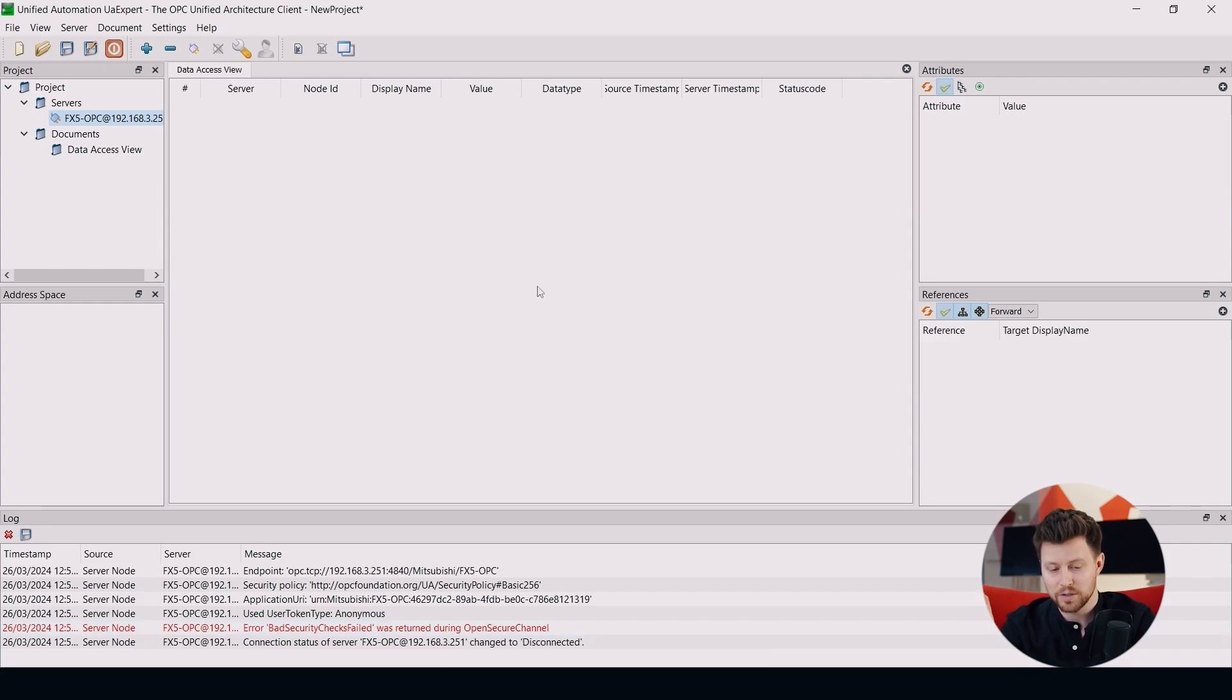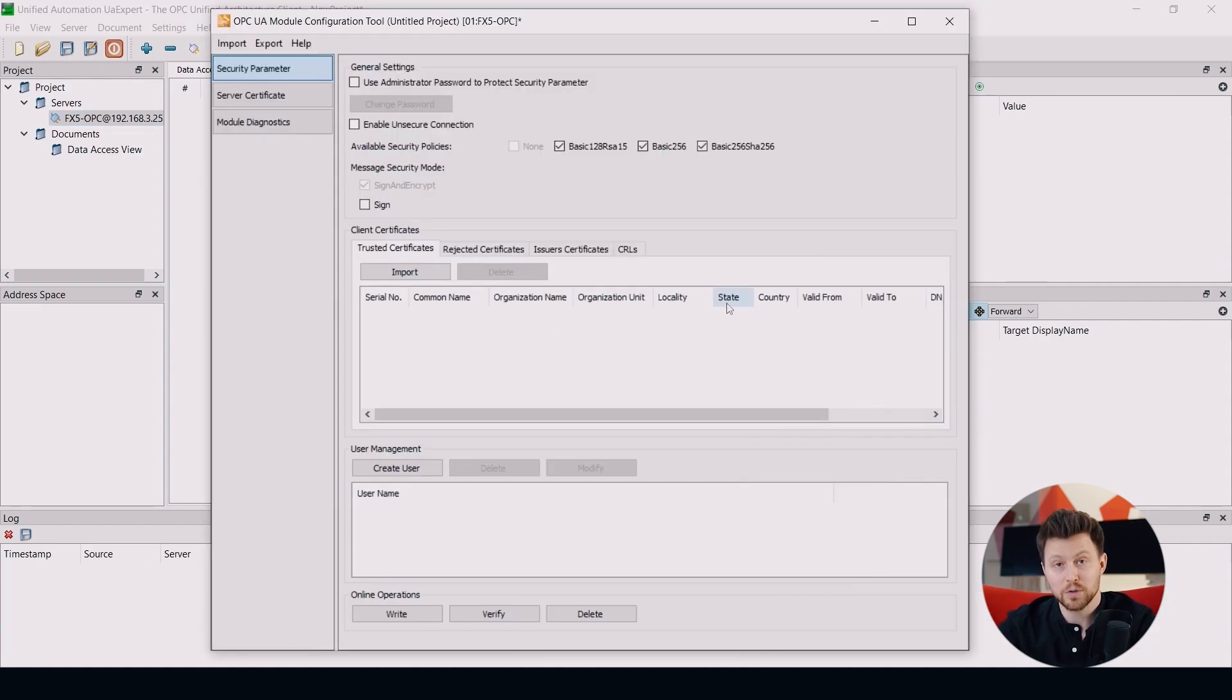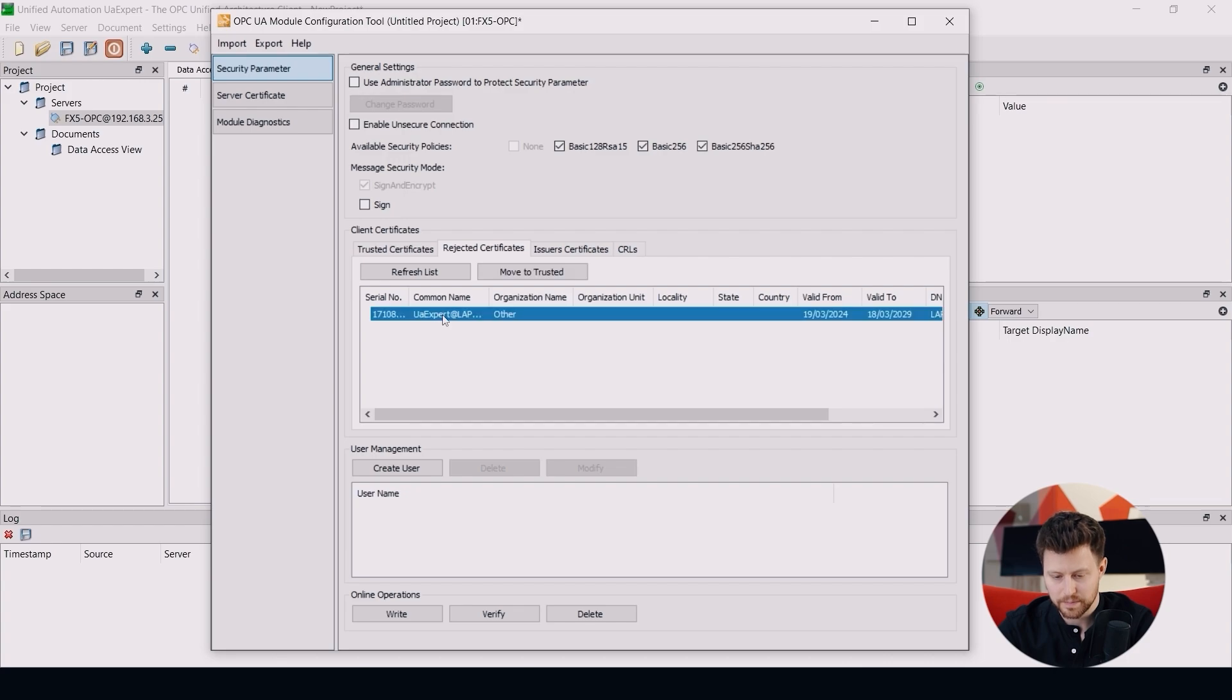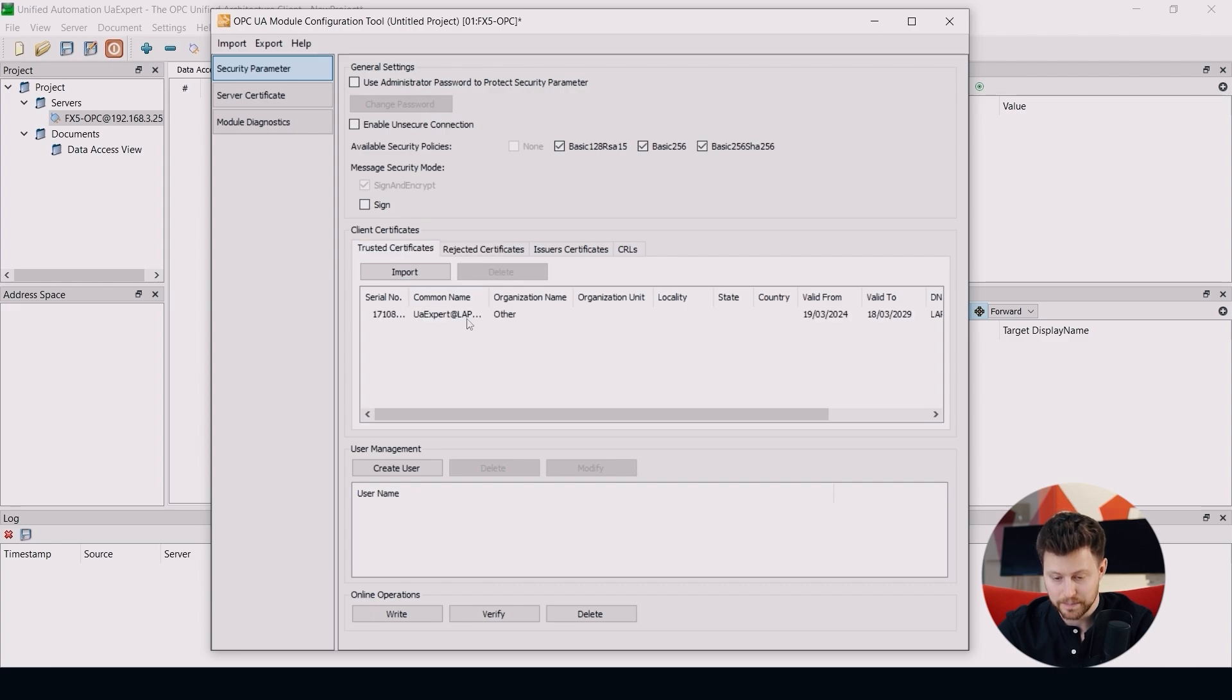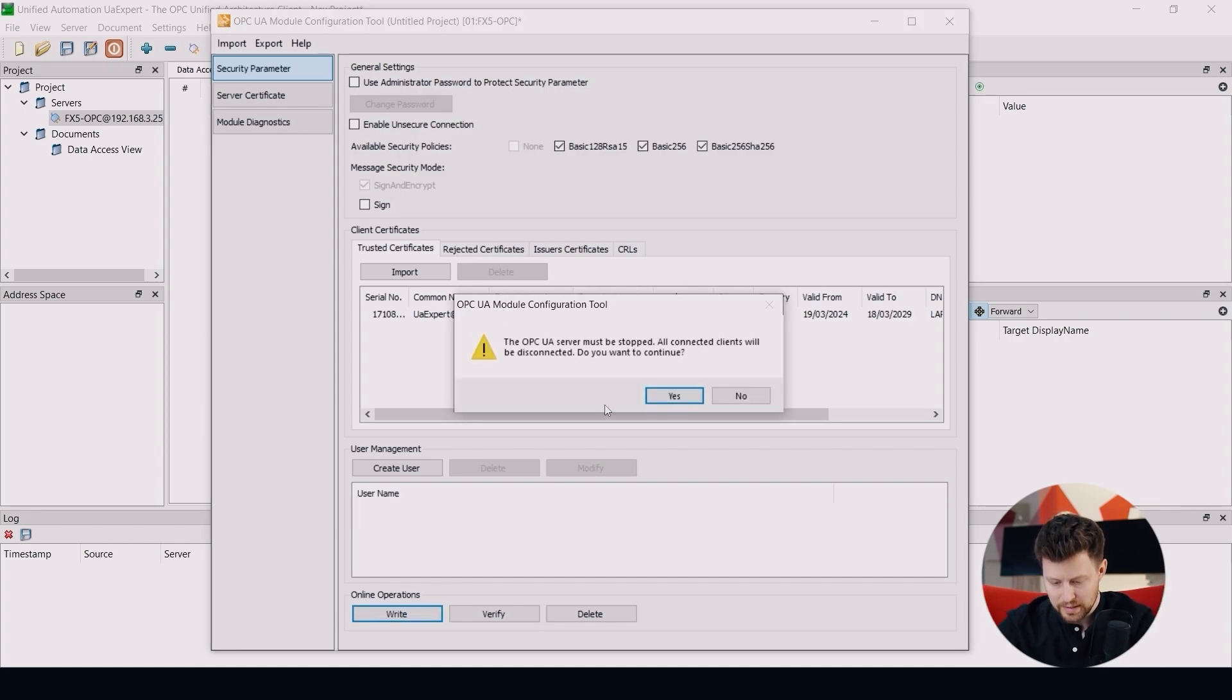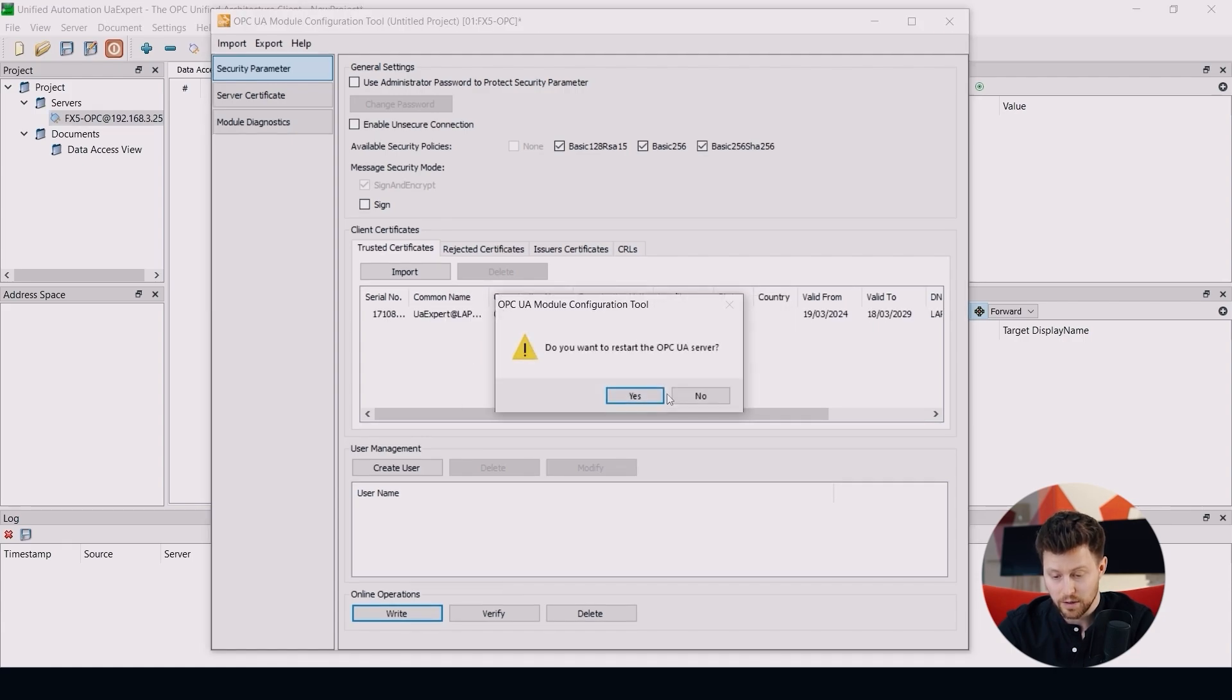So let's open OPC UA module configuration tool again. And here in the rejected certificates we will find our UA expert client. So let's click on this and move it to trusted. And right now the communication is trusted on both sides, server and client. So write these changes to our module and restart the OPC server.